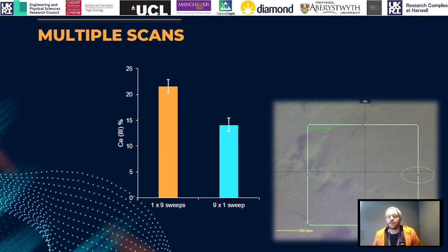There's a lot of really nice functions in modern spectrometers. Again, Thermo and Kratos both have functions where you can put in area scans and very quickly get multiple analysis regions of different areas, which can then be combined into a cumulative plot in CasaXPS, so you can get the good signal to noise of multiple scans but avoid the downside of having a reduced material.